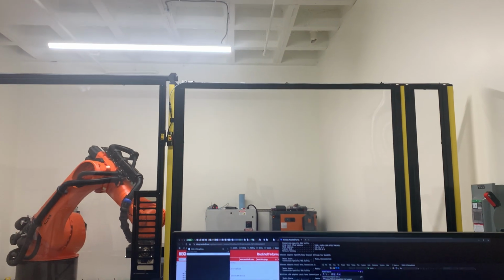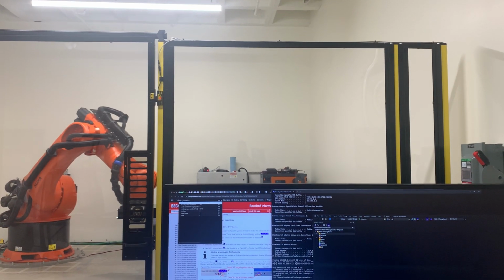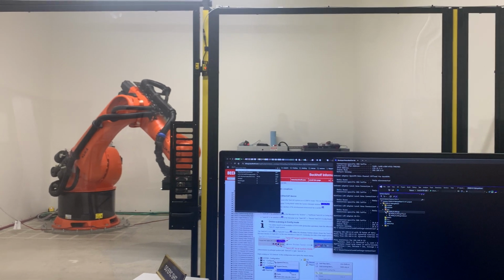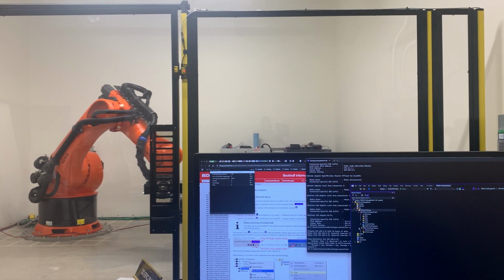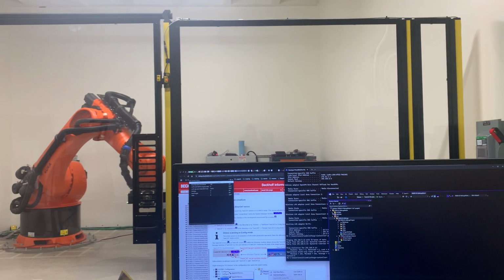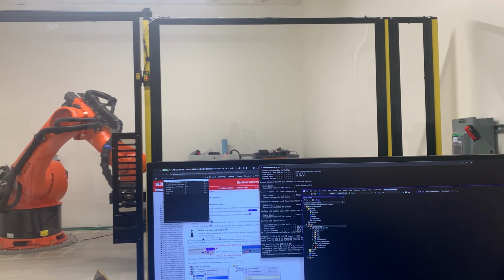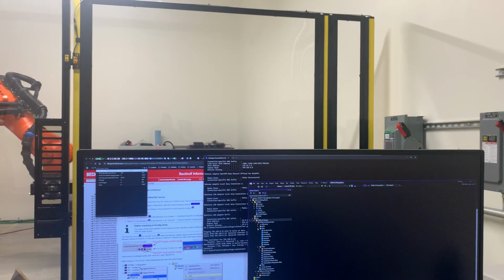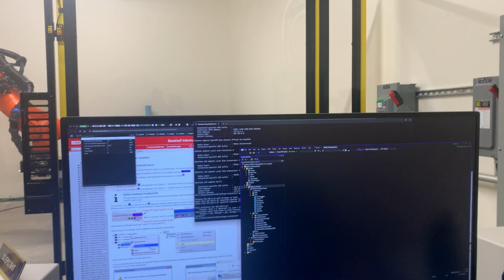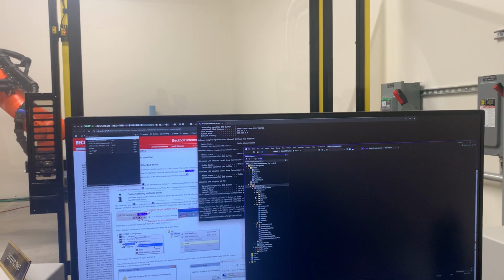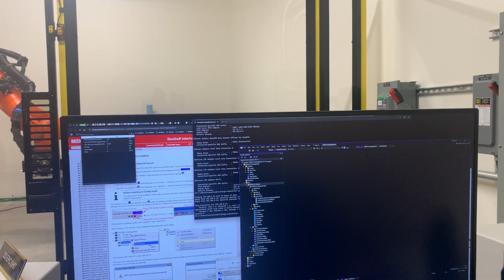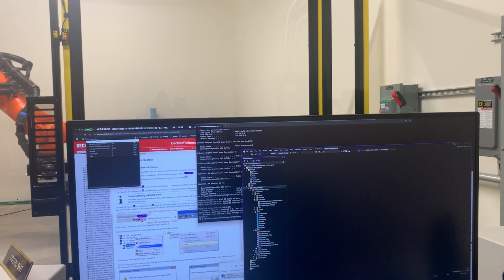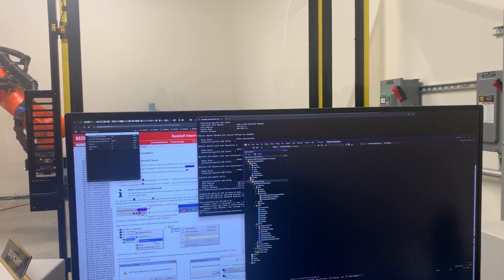That's just a watch window. You can see that's the watch window I had watching some variables. But there is your PLC code. So the POUs and all that stuff, that's where all the code is. The GVLs are the global variable lists. DUTs are data types. So if you want to create your own structures and things like that, or enums, that's what's useful. There's the code.